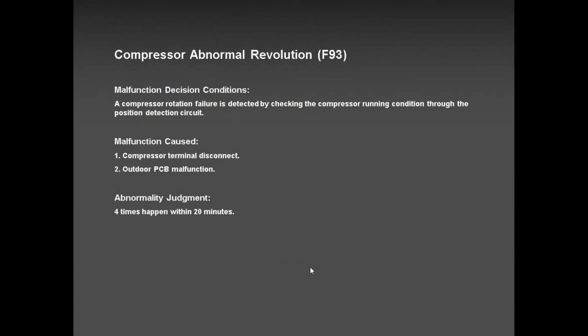F93. If you get this error code, my friend, and the unit is not resetting, the compressor is gone. Again, I have not seen this error code, but it's there, and that doesn't mean it will not happen. At some point, some years down the road, it will happen. And when you get that error code, the compressor is gone.